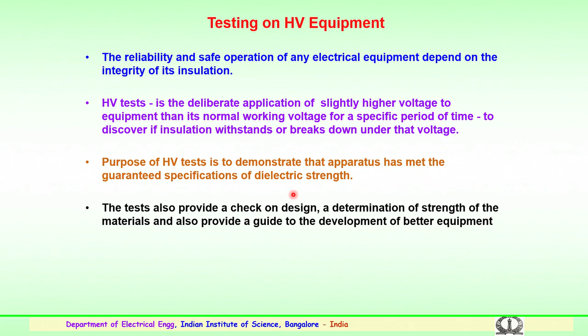Also, these high voltage tests provide verification of the design, a determination of the strength of the material, and also a guide to the development of better equipment in case the insulation is not able to withstand for a particular equipment. This will definitely help manufacturers to improve the equipment design and give better performance in field conditions. With that, we will look into the philosophy: why high voltage testing is important and what is the philosophy behind the testing of these equipments.